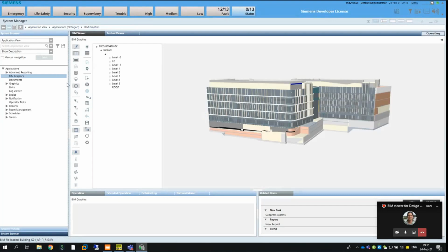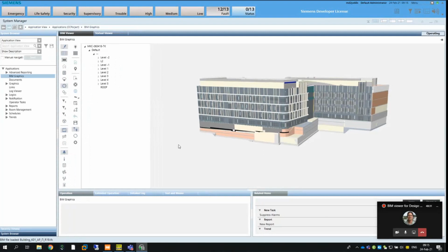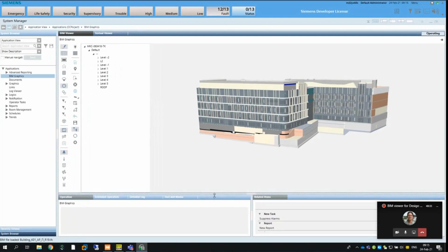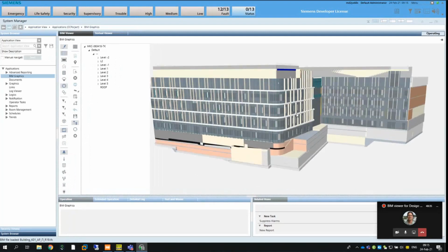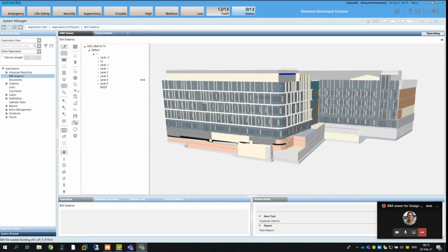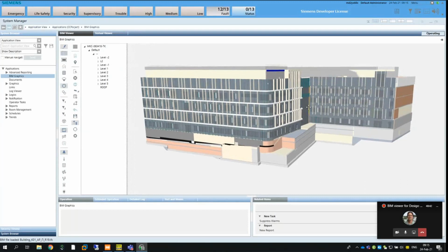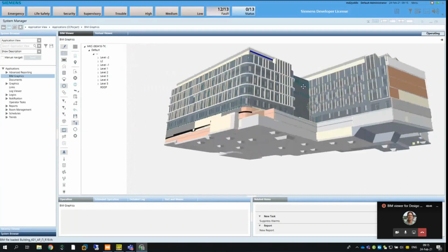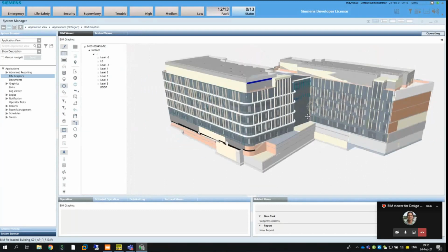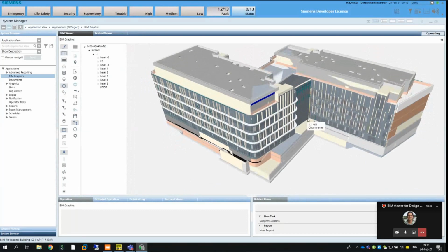So yes, David, you're correct. Basically, we can import multiple IFC files, and then the content of one IFC file will be the amount of graphical elements you will display. And so if you would end up using one large IFC file for your campus, let's say with 5 buildings, then you will have considerably more problems than if you would have it split up in 5 IFC files, one for each building.